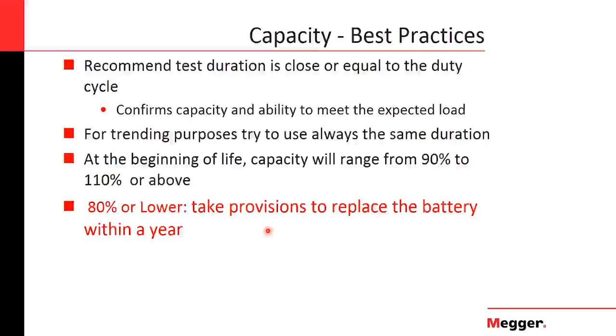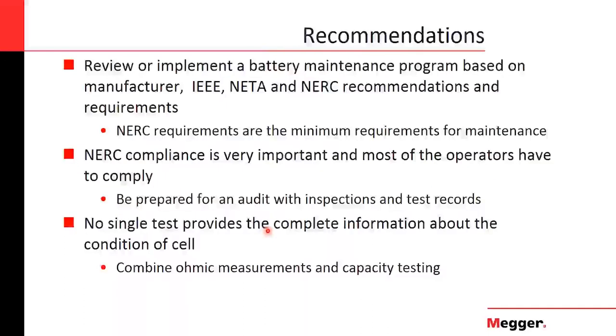NERC is really important. Batteries are really important. They are very important for the system. So if you are in one of these entities that need to comply with NERC, you definitely need to implement a battery maintenance program. If you don't need to comply, it's still a very important asset that you want to maintain. So try to review, implement, or improve your current battery maintenance programs using the IEEE, the NERC, and the NETA recommendations. As a minimum, you need to comply.